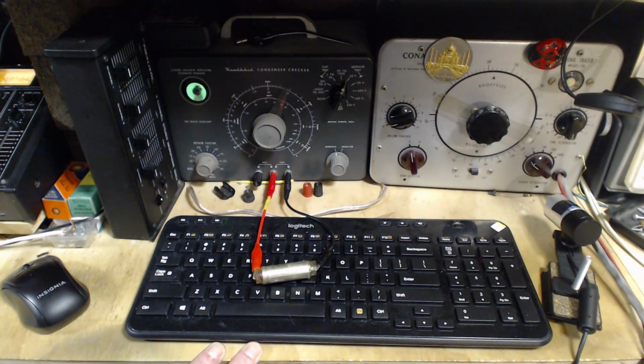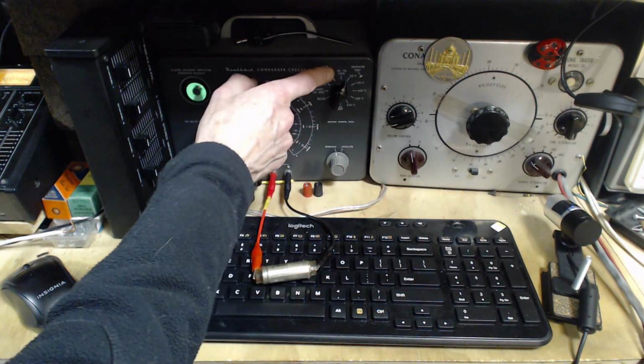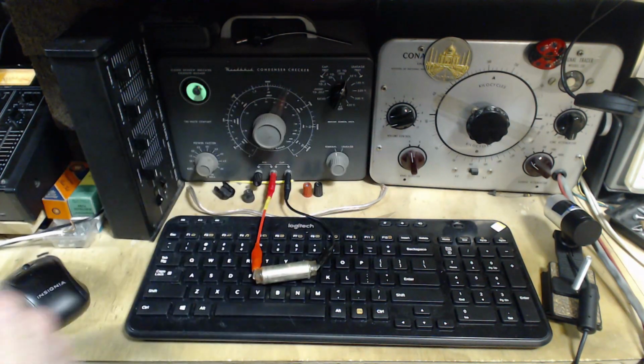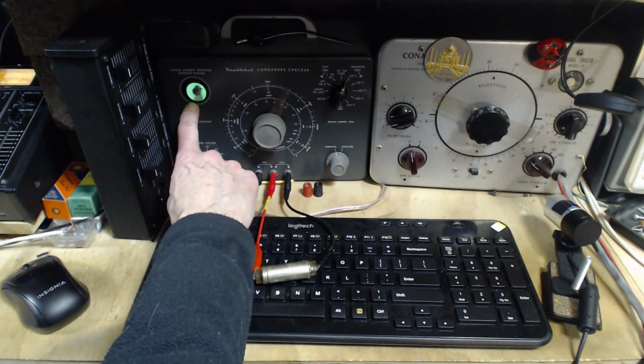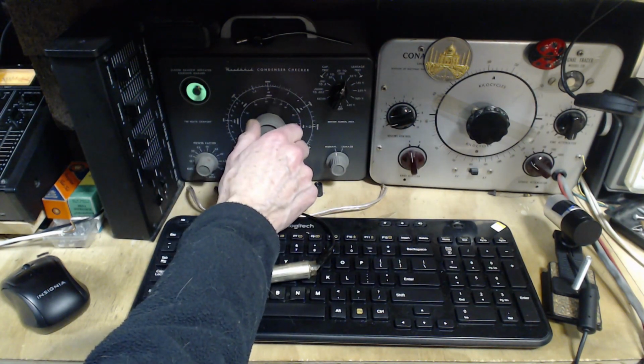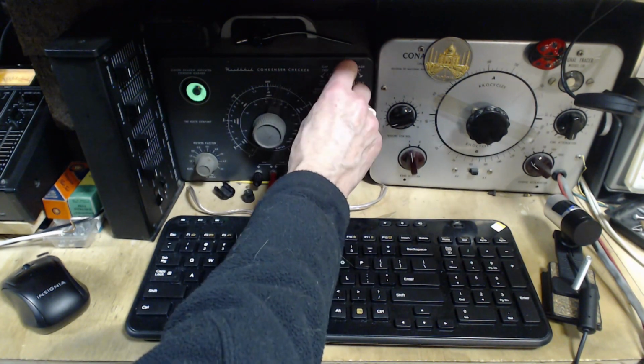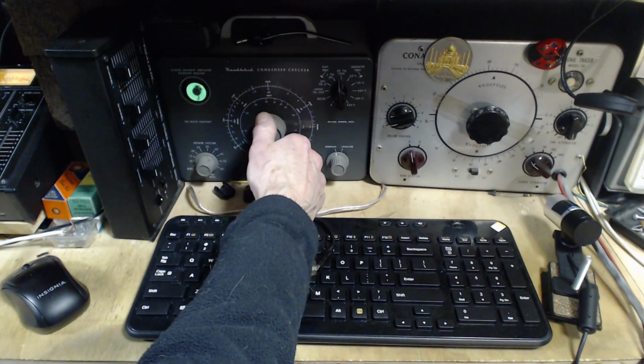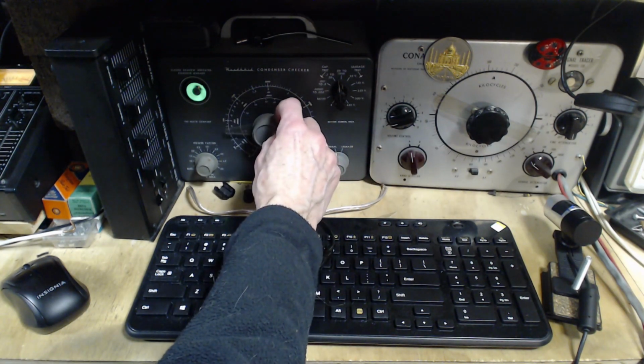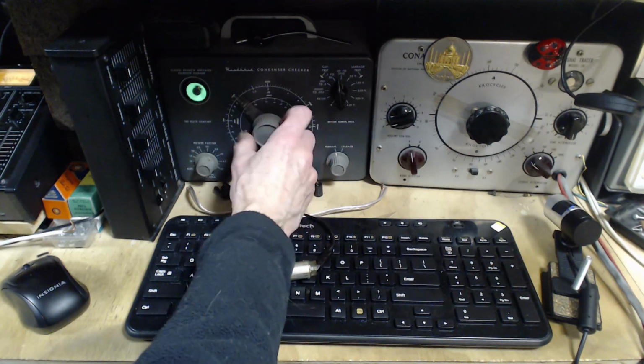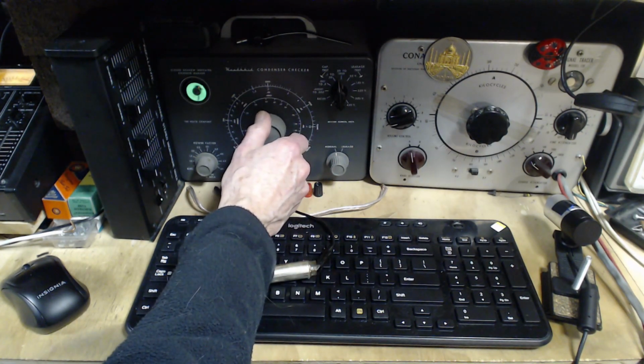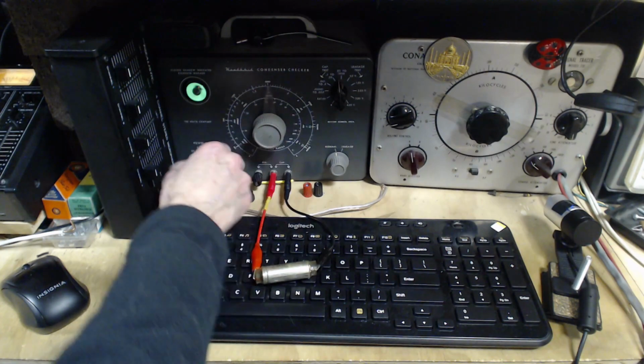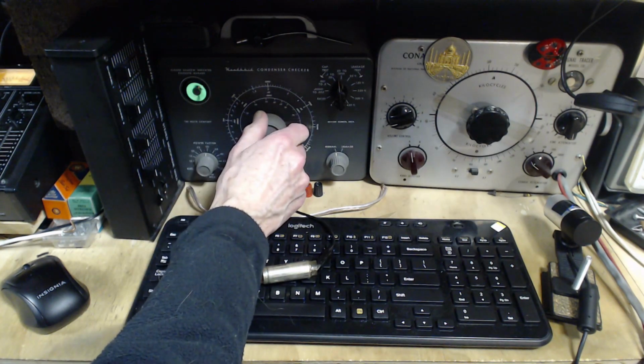And we're going to test its capacitance. 500, wow, that might just be a little high for this machine. 20 to 1,000, so we've got a scale here it'll do it on. We're going to adjust this until the eye closes. So this is giving me a very bad feeling. The eye is staying closed, I think that's a bad feeling.